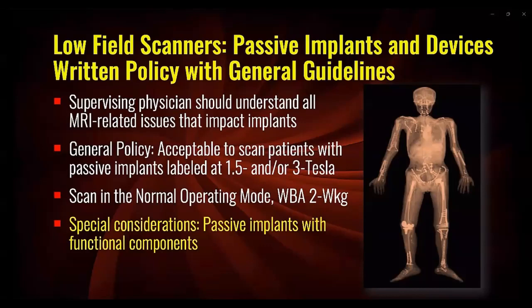Considering the effects of force, torque, and MRI-related heating, patients with virtually all passive implants labeled at 1.5 and/or 3 Tesla can be safely scanned on MR systems operating below 1.5 Tesla. This includes scanners with horizontal or vertical fields, or put another way, fields that are longitudinal or transverse to the patient undergoing MR imaging.